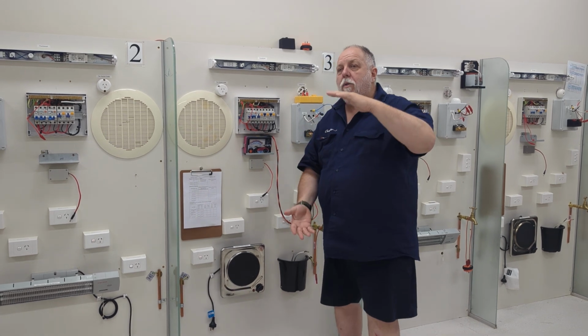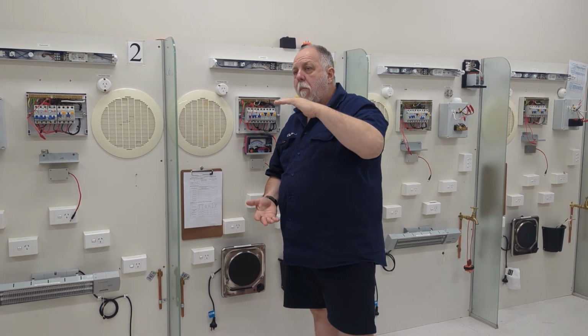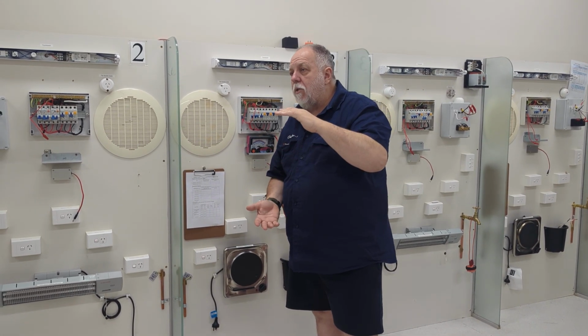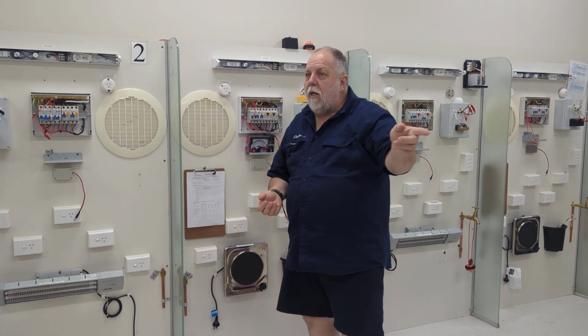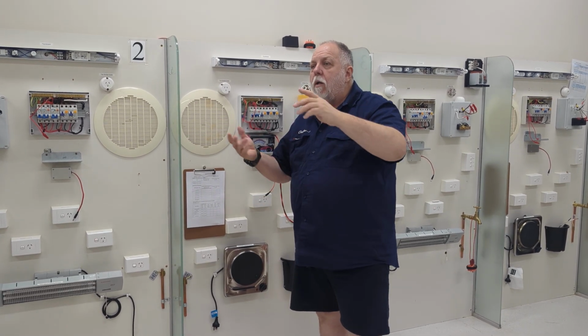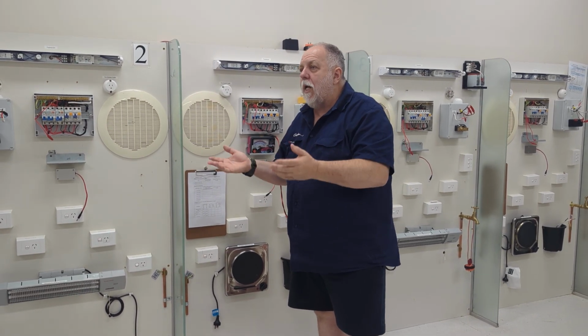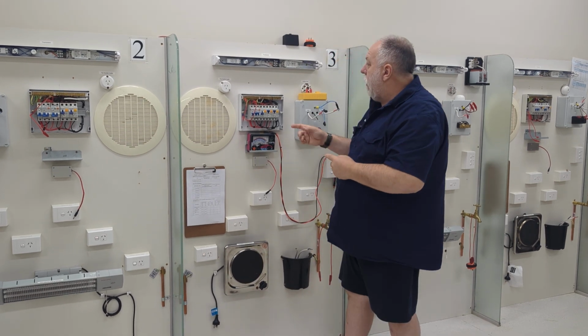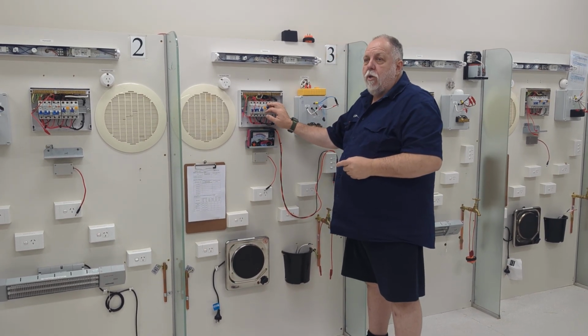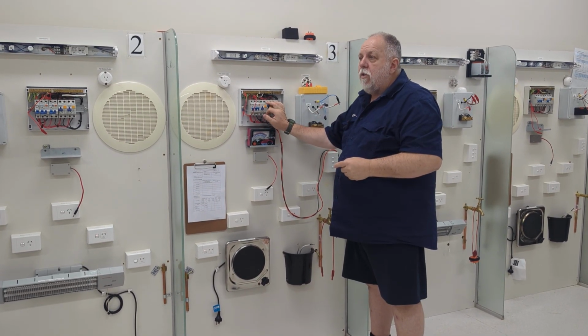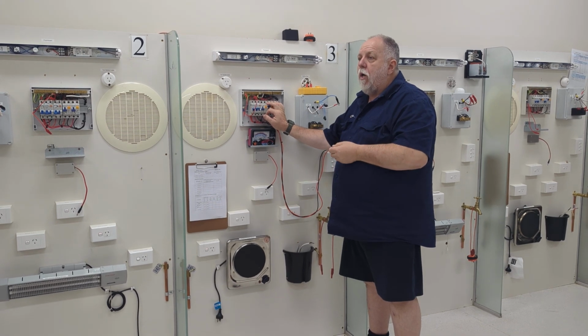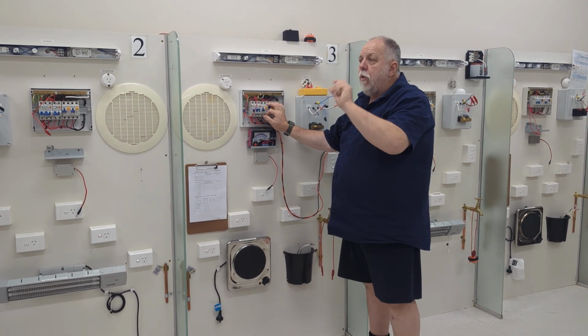You've got to remember what happens as the cable gets bigger. The resistance becomes less. So at the mains, going out back to the start point, all the way through the mains, we don't have a problem because our cable's quite big. The choke point we get is on the final subcircuit. If we don't have that resistance right, it becomes a choke point for our current to operate in that loop to operate the circuit breaker.